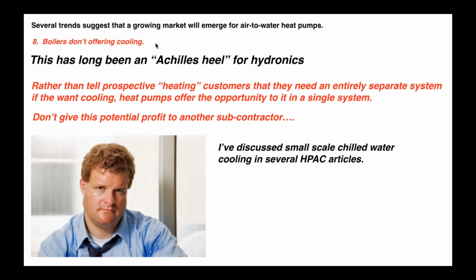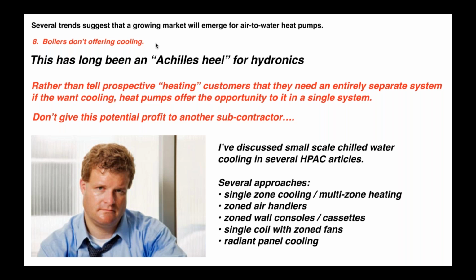So chill water cooling is something we've talked about in several past HPAC articles. There's several different ways to do it. Right now, I don't want to get into those in detail, but basically you're producing chilled water with the heat pump, and you're going to route that chilled water through some type of distribution system. It might be zoned, or it might be a single zone. You know, you could do multi-zone heating and single zone cooling, or almost any combination there. But this gives you the ability to offer your customers cooling, which you can't do with a boiler.